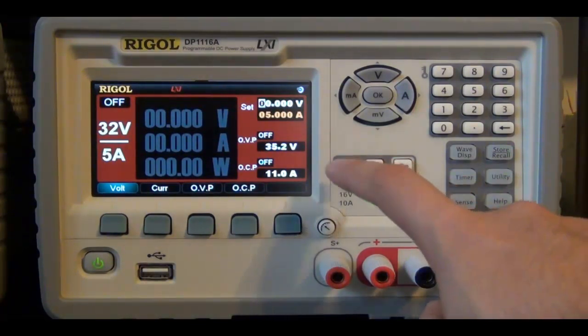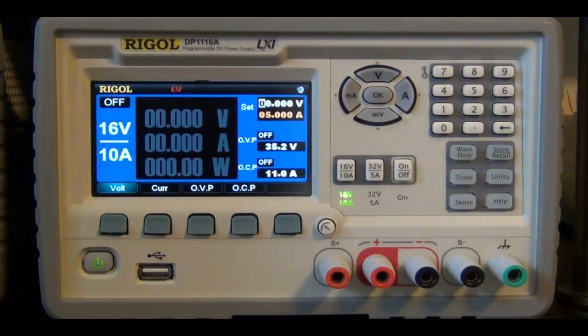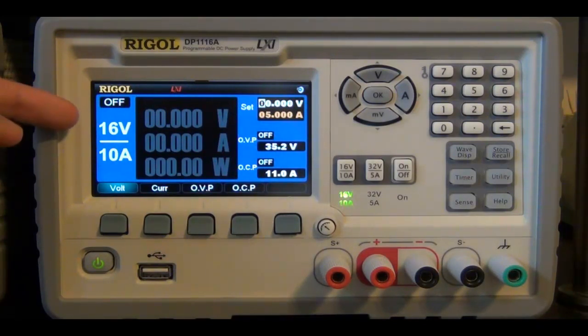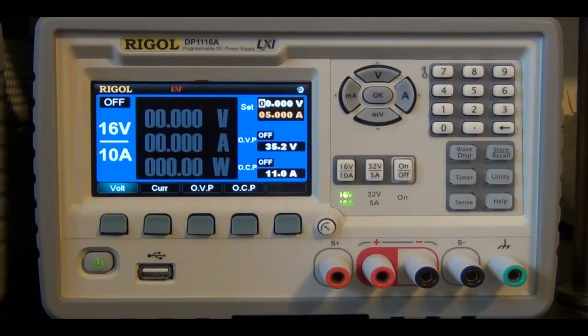So let's try this. For example, I can go to this 16 volt 10 amp mode. Everything stays the same, but the background color changes and the 16 volt 10 amp symbol appears here. So you can see if it's red, meaning that you can go all the way to 32 volts. And if it's blue, it can only go up to 16 volts. So it gives you an idea, sort of without having to look at the numbers, if you're looking at it from the corner of your eye, you can tell from the color code.